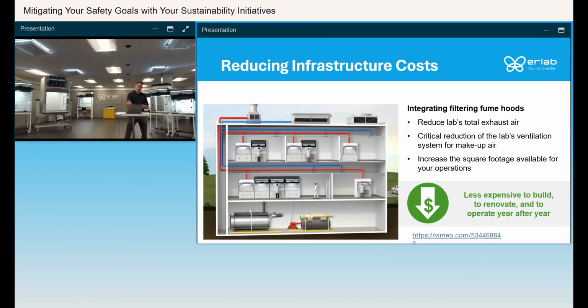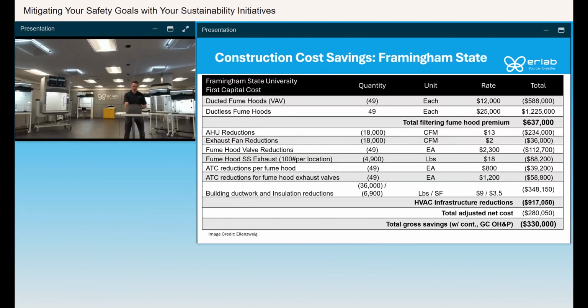So in this example, you look at all the hoods where there were multiple hoods in there. If you have too many ducted hoods in a small space, you're going to overventilate the space because of the required makeup air. So adding ductless fume hoods once you reach that minimum air change rate will save significant amounts of energy, but also in the initial design, it's going to allow you to have smaller mechanical equipment, reduce the overall size. So you can see the size of the chiller and boiler in the basement, much smaller. There's one less exhaust stack on top of the roof. The air handler and the cooling tower are smaller. And also even the ductwork, the supply and return ductwork, can be smaller. So you can save significant upfront costs on new construction with ductless fume hoods.